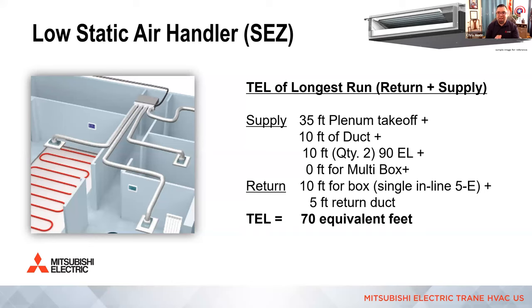I've said it like 3 or 4 times. I know I'm beating that horse, but I need to make sure you don't do this design on these other styles, only on low-static. So if you look at that box, there's a box that's typically 8 to 10 inches in depth off of the front of an air handler, the low-static SEZs. And then they're taking those takeoffs right off the end of the box.